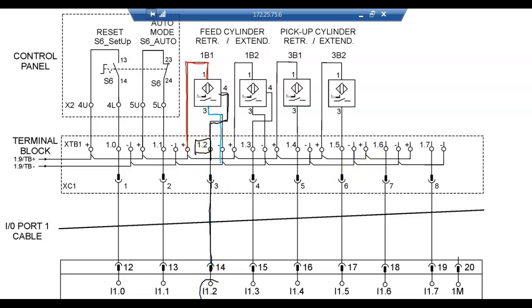So it's coming down here to input 1.2, on my terminal board it's going to be 1.2. But it's a 3-wire sensor - this is a magnetic sensor, but it's only got 2 wires, so this has got to be a reed switch.